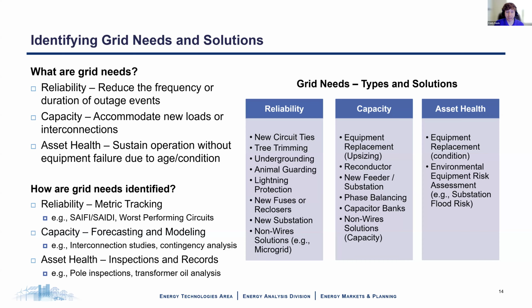Grid needs for capacity are generally identified through forecasting and modeling. So these are your interconnection studies, your power flow analysis, contingency studies, load growth projections and forecasts, et cetera. And then on the asset health side, these are generally outcomes from inspections and record keeping. So you may have pole inspection programs, transformer oil analysis, dissolved gas analysis, different types of sampling to check on where assets are in their life cycle.